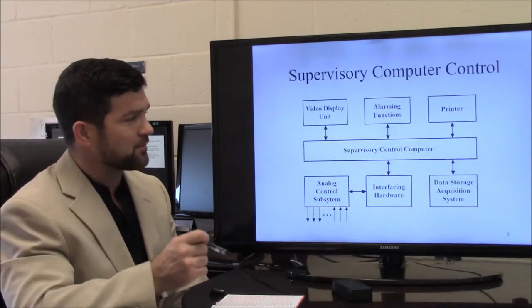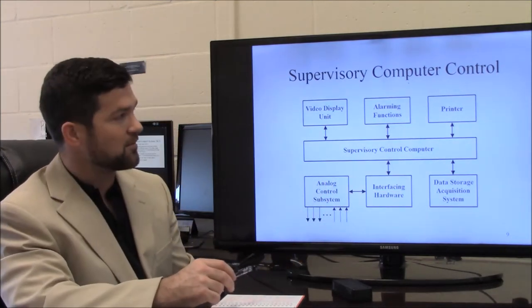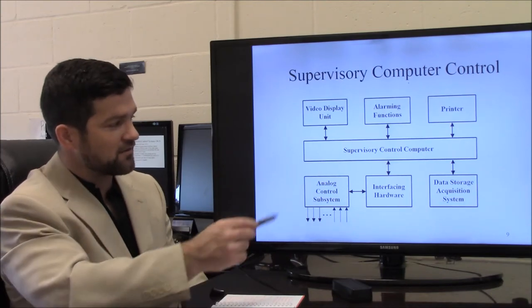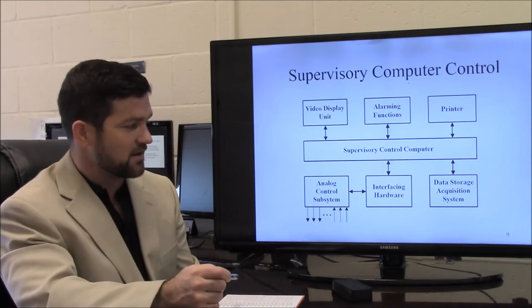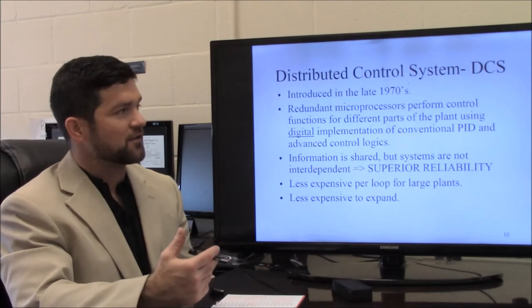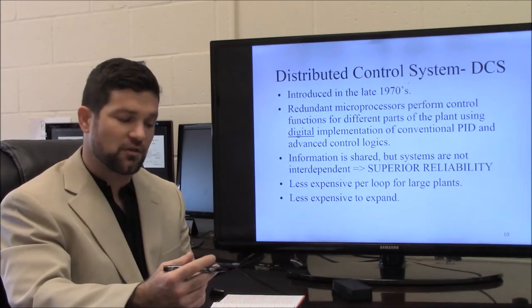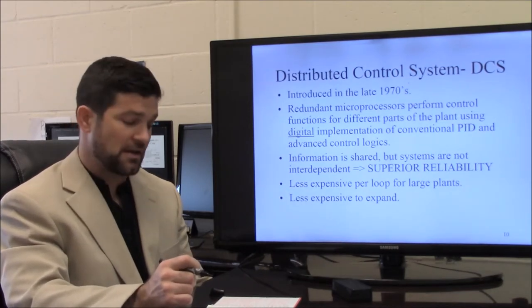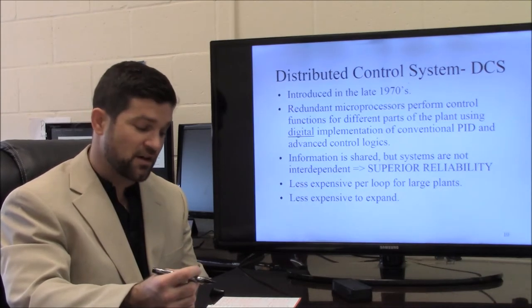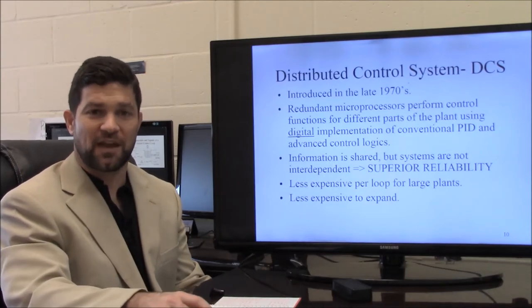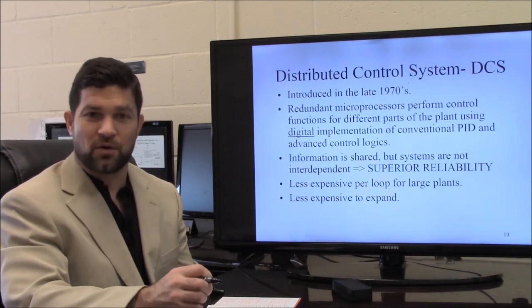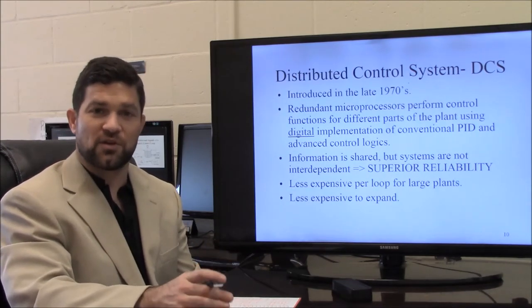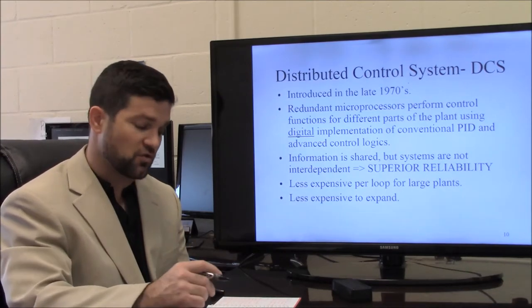On the supervisory control diagram, there is a supervisory computer in the middle connected to all video displays, alarms, printers for troubleshooting, and data storage. With the development of distributed control systems in the 1970s, we're approaching the level of control we would develop today. DCS systems integrated redundant microprocessors, so each individual control system could effectively have its own control loop. Data was stored digitally — analog signals from the transmitter were converted to digital signals, stored and processed within a central unit, and used by controllers to control processes individually.